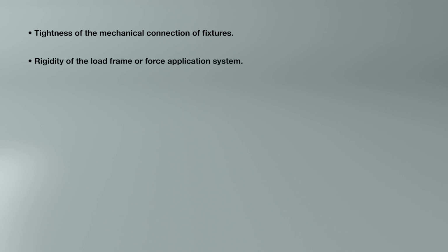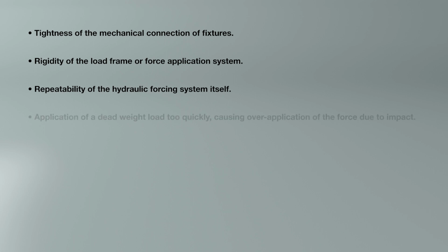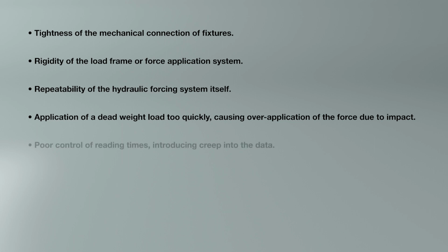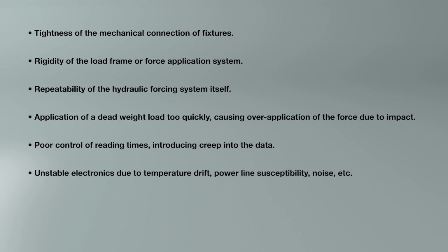Repeatability is affected by any one of the following factors: tightness of the mechanical connection of fixtures, rigidity of the load frame or force application system, repeatability of the hydraulic forcing system itself, application of a dead weight load too quickly, causing over-application of the force due to impact, poor control of reading times, introducing creep into the data, unstable electronics due to temperature drift, power line susceptibility, noise, etc.